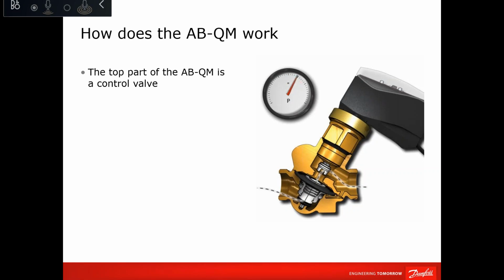If you want, after 5 or 10 years, if your coil efficiency is dropping, you can increase that 10%. Even if you put it in since day one, it will not affect anything, because the actuator will modulate the spindle regardless of the load demand.